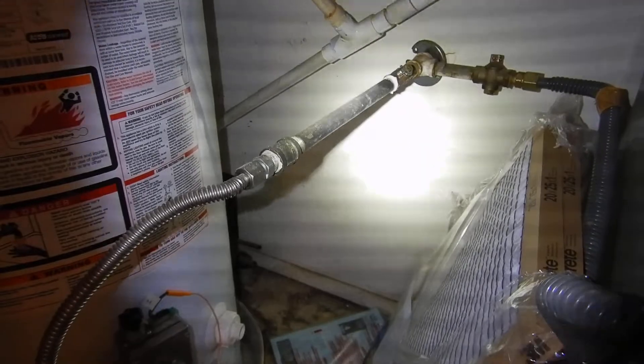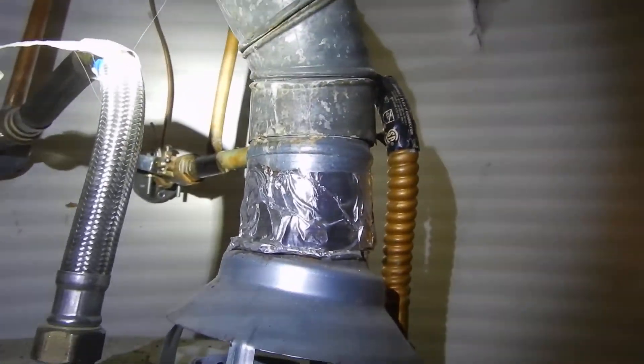Unit's 10 years old. Do not have a sediment trap for the gas. We've got a screen. And our flue's been sealed with tape.